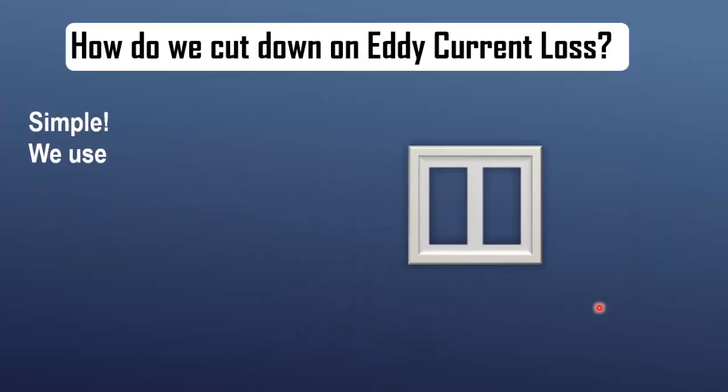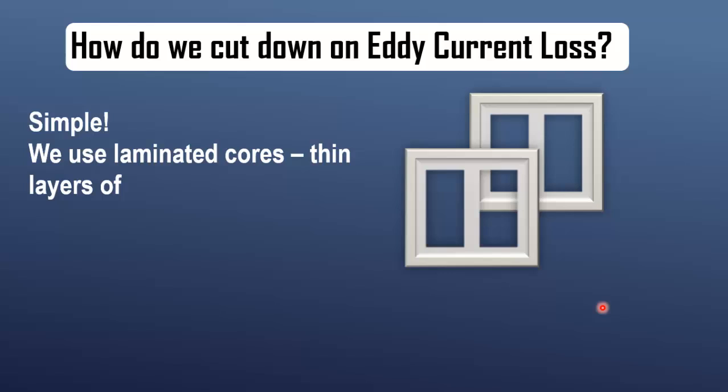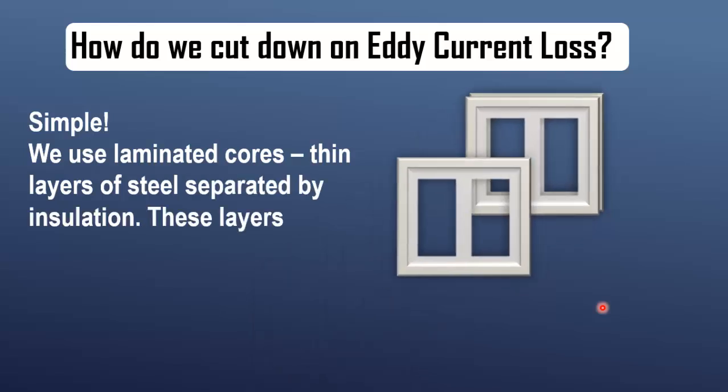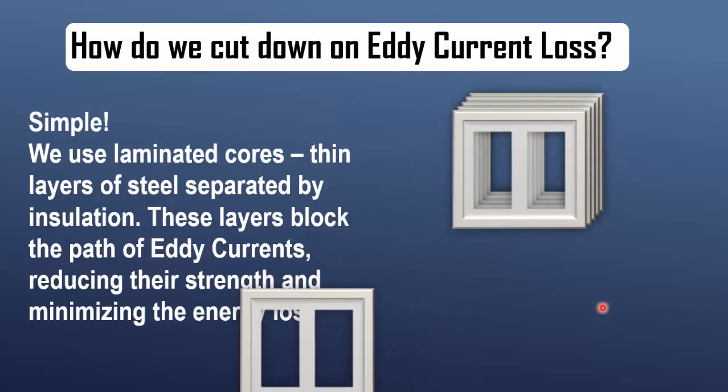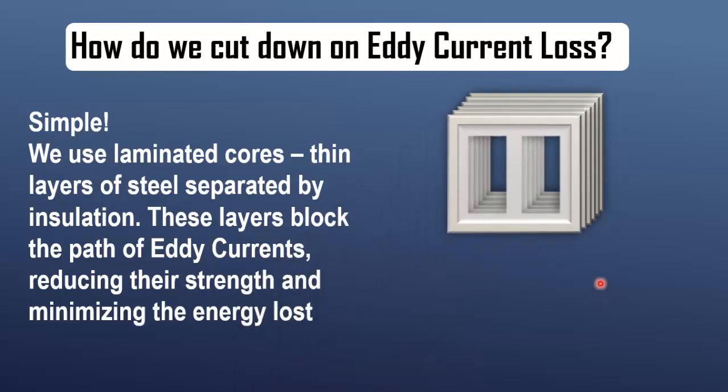Now, how do we reduce eddy current loss? Well, since these currents flow through the core material, we use laminated cores. By making the core from thin, insulated sheets, we restrict the flow of these currents, reducing the loss. So laminating the core material helps keep eddy current loss low.